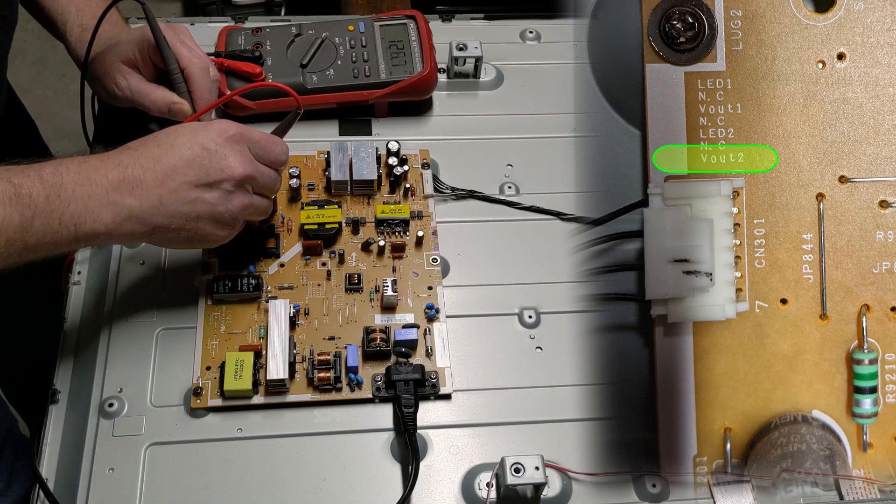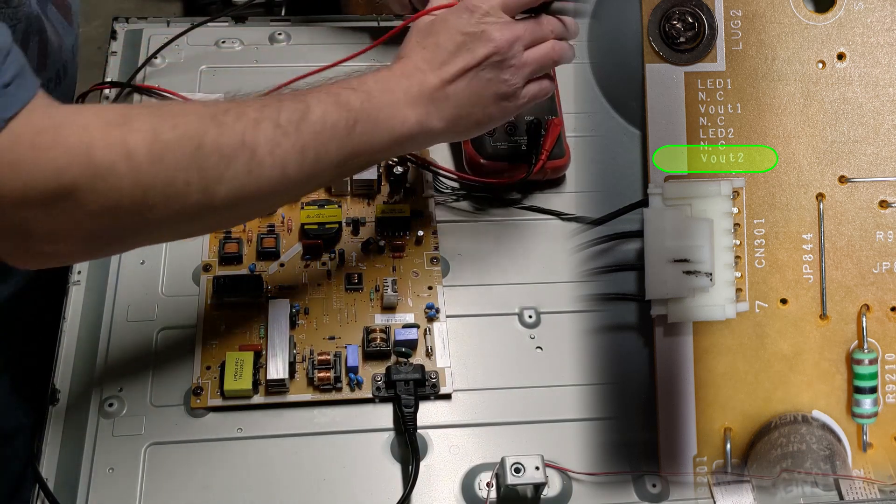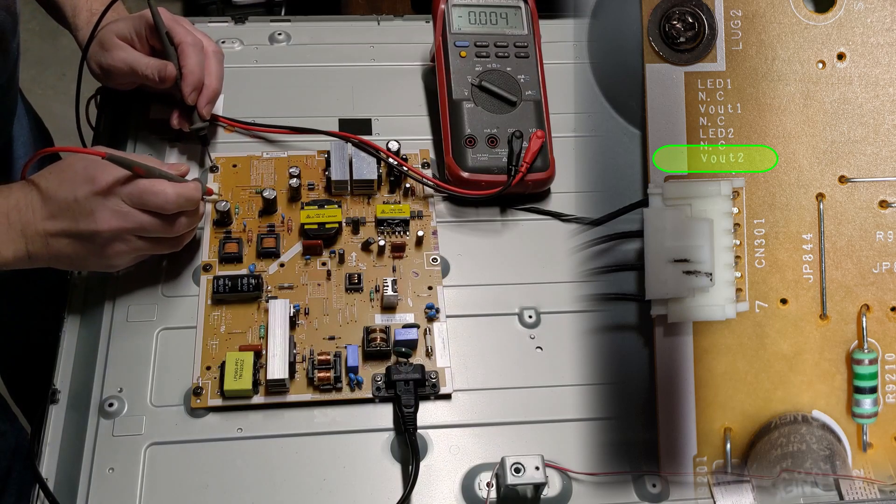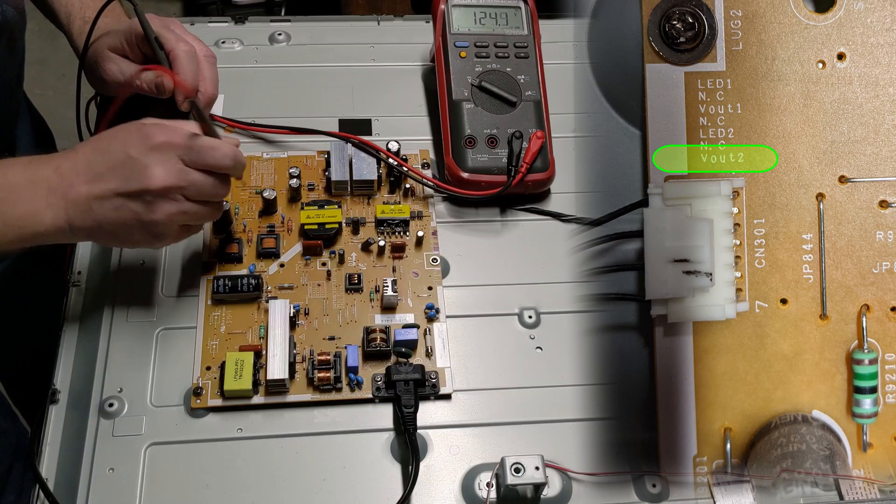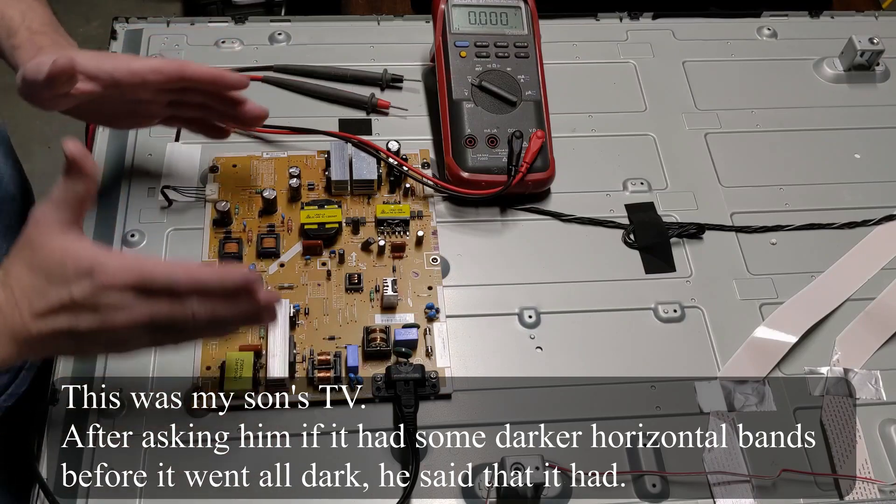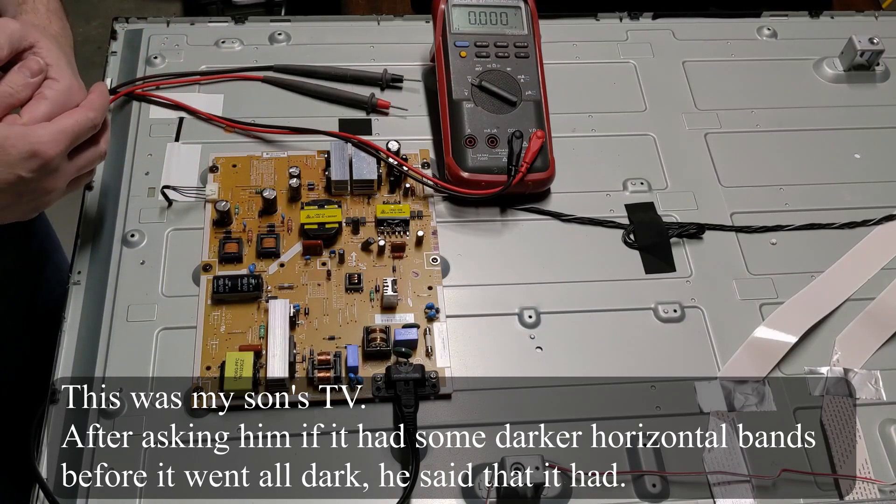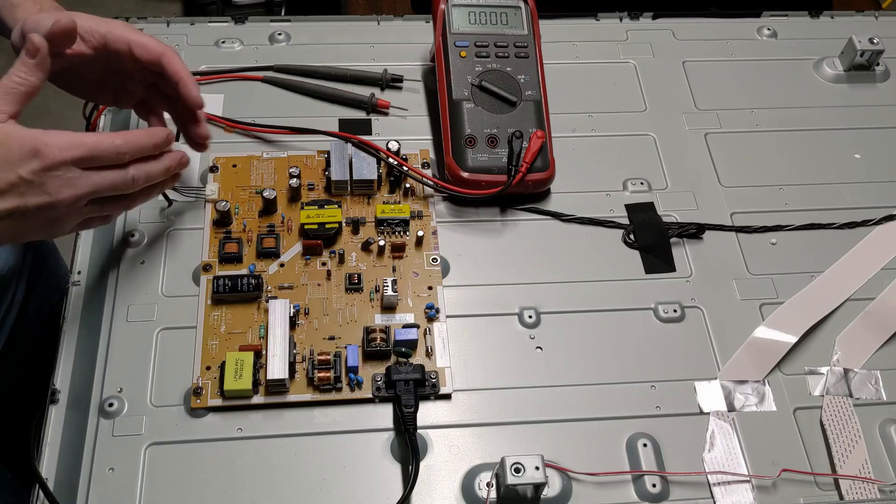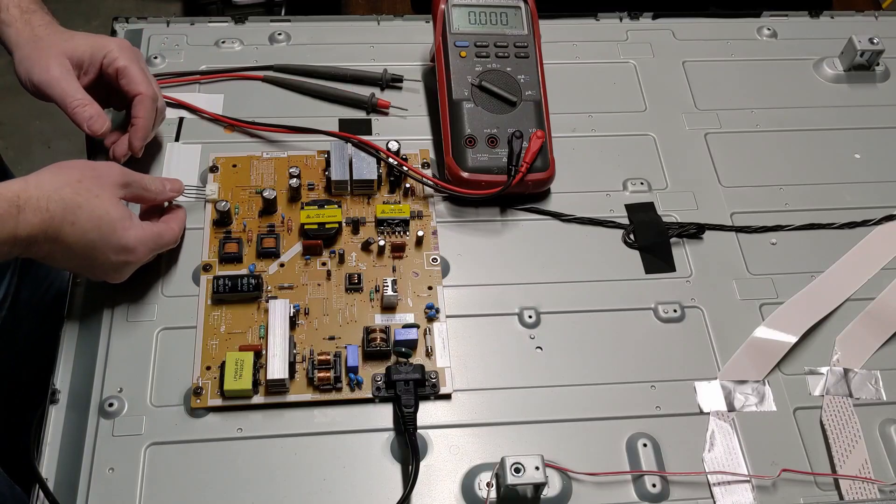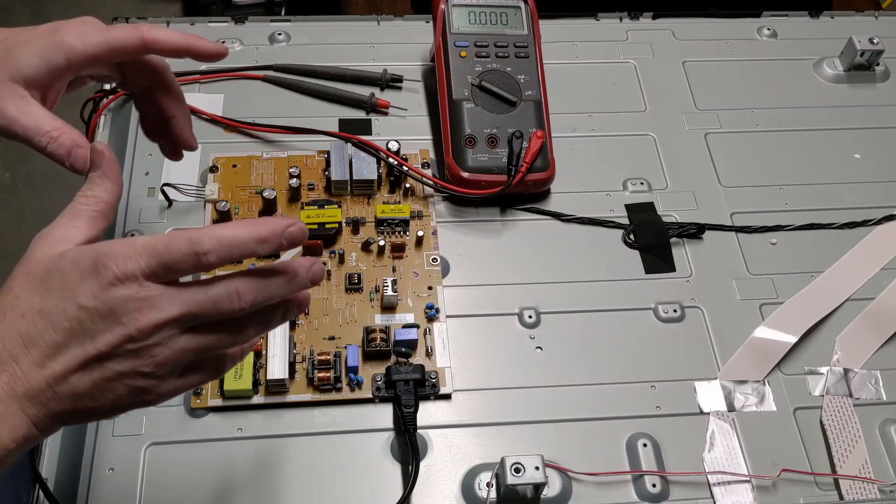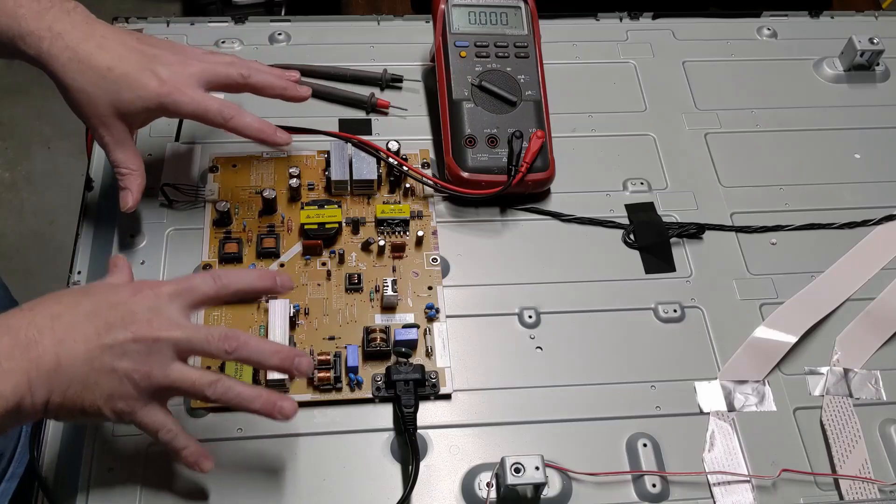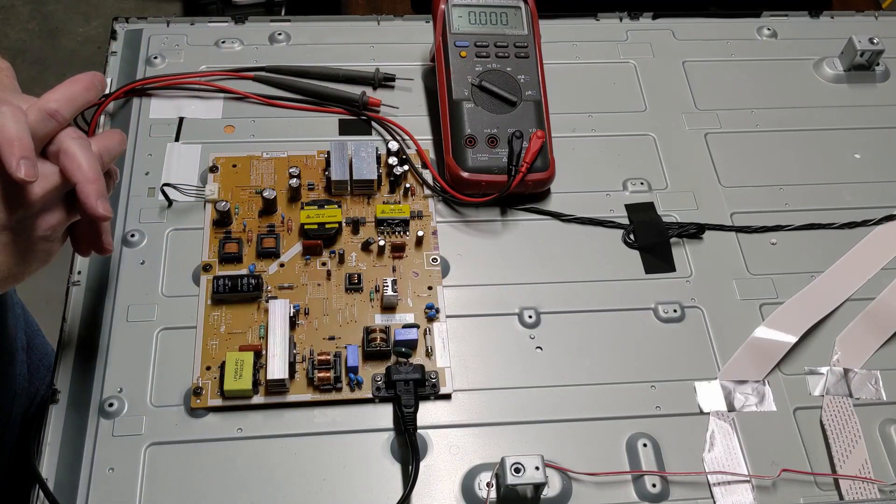We have LED one: no connection. Voltage out one: no connection. LED two: no connection. Voltage out two: 120 volts. You can see it's not very stable - it's 120 to 128 volts, not stable, and a little bit higher than it should be on a current control. Voltage out one is doing the same exact thing. It looks like both banks of the LEDs - LED bank one and LED bank two - are both open circuit, because it should be a constant current with somewhere around 100 volts output.